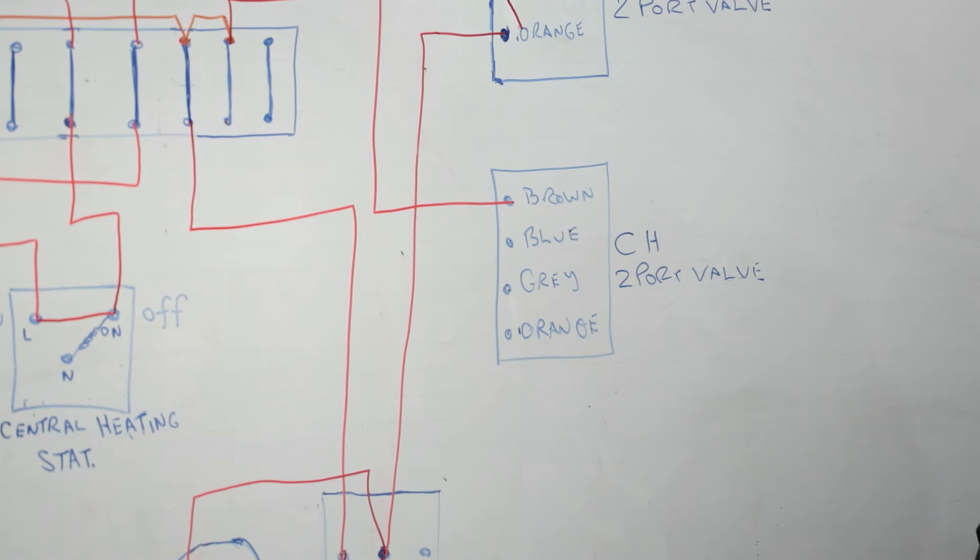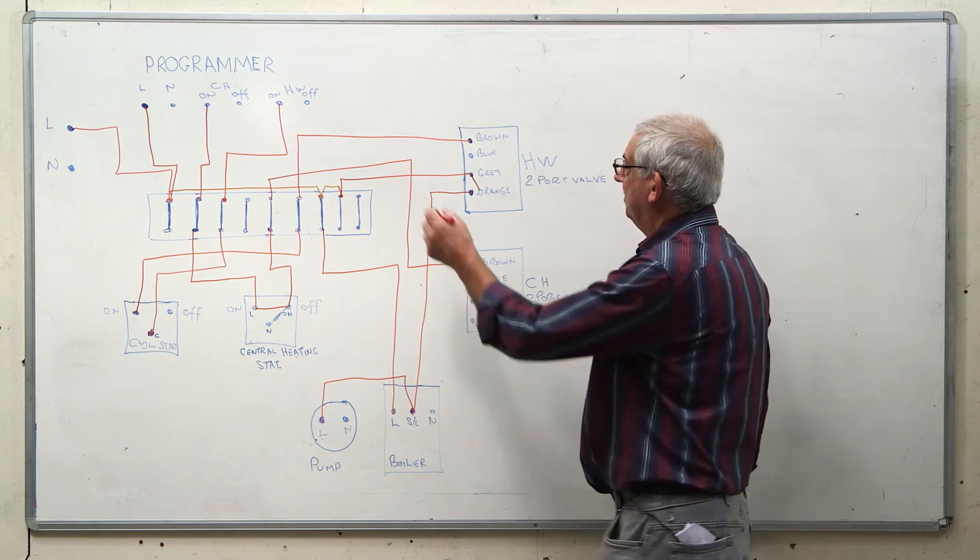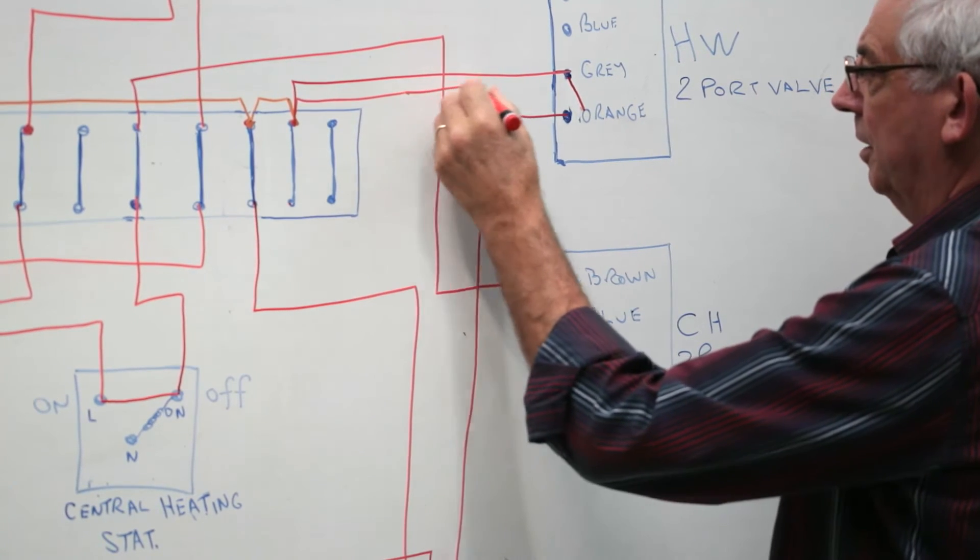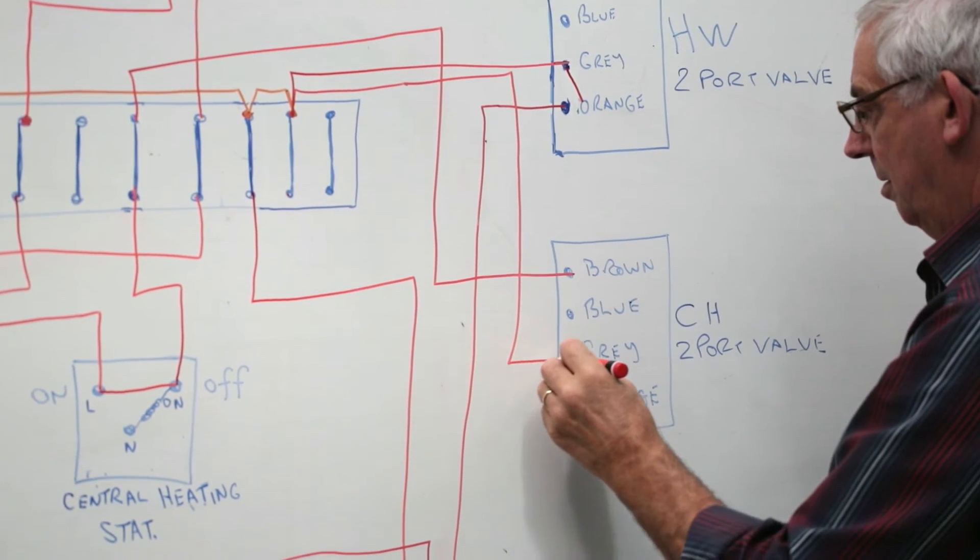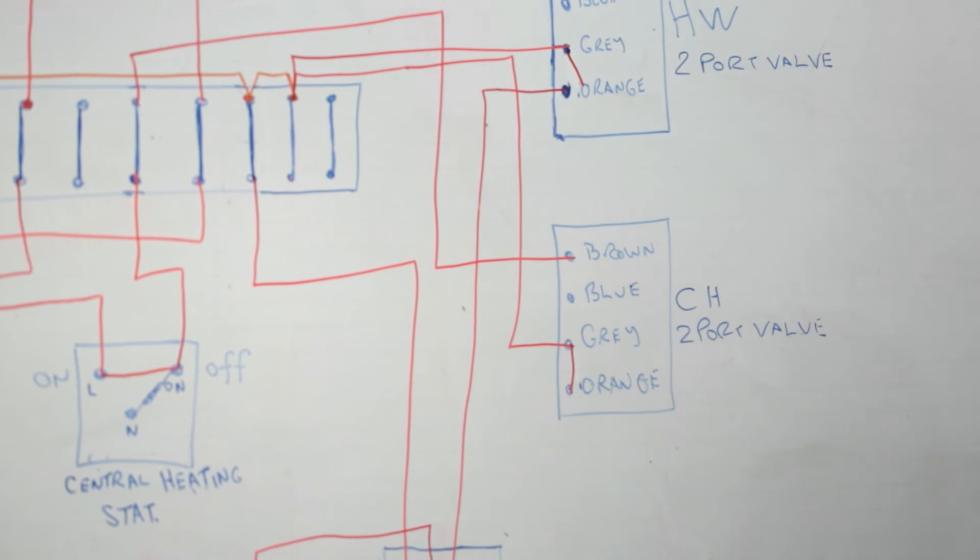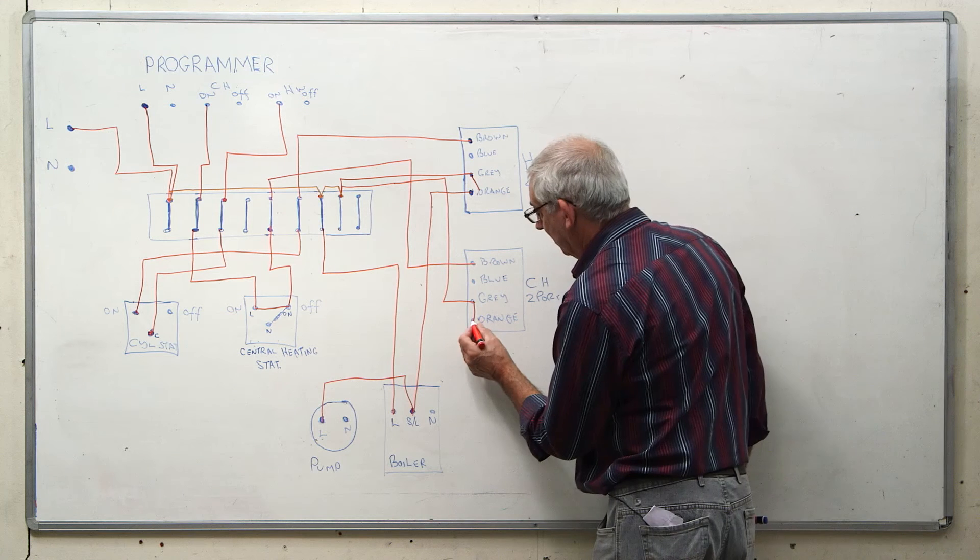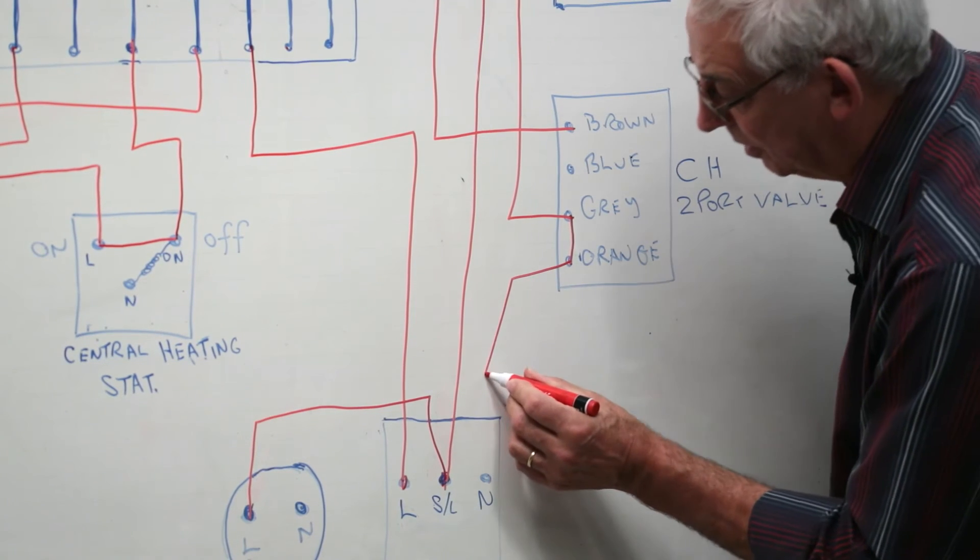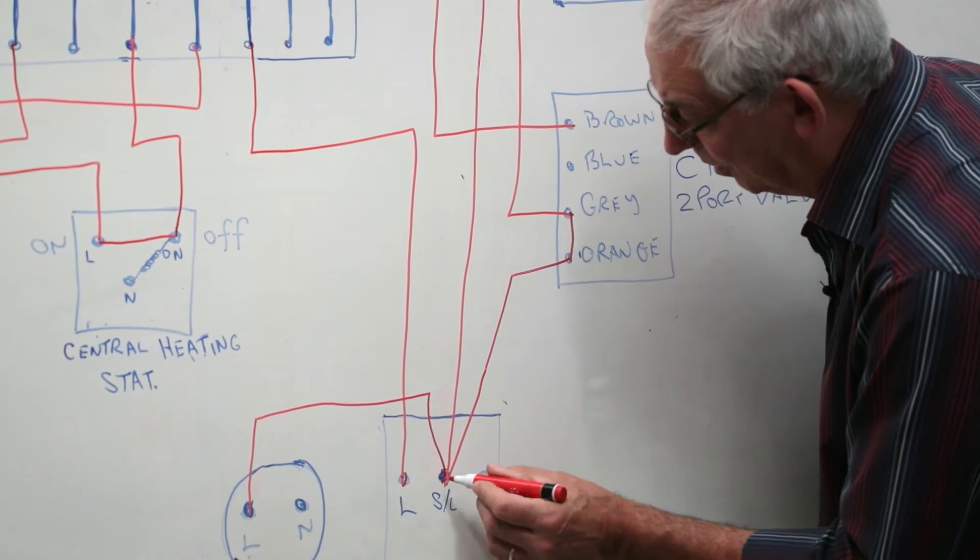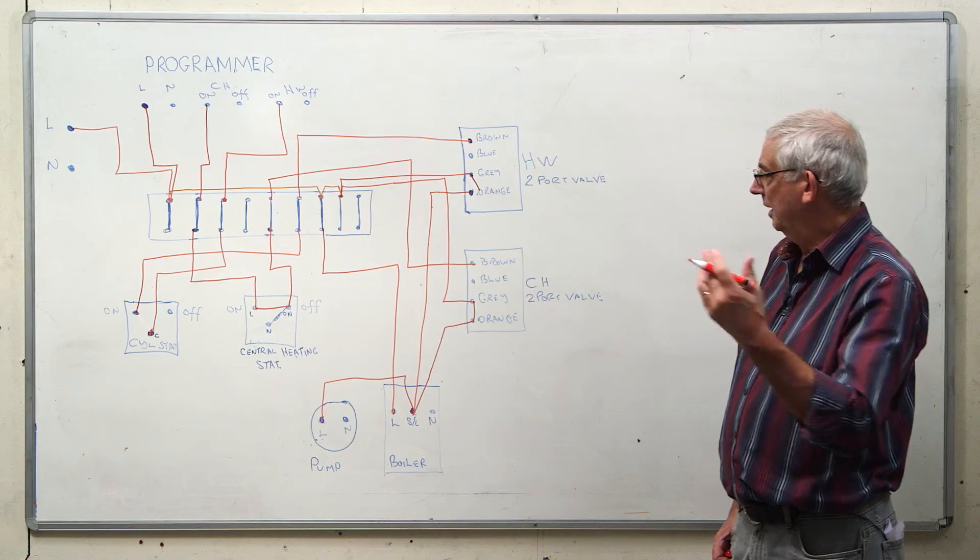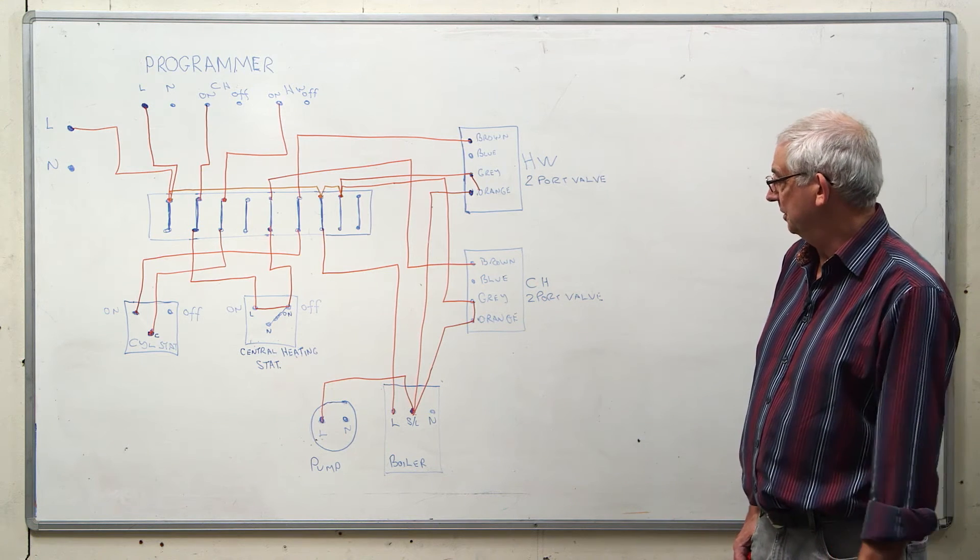The two port valve now opens. I've got a permanent live to the grey here as well. When the two port valve opens, it closes the micro switch to the orange. The orange now sends a signal down to the boiler which of course then sends a signal to the pump and everything works as it should do.